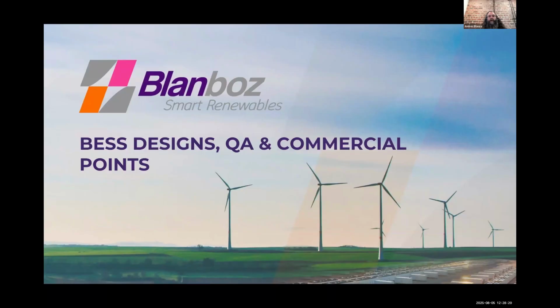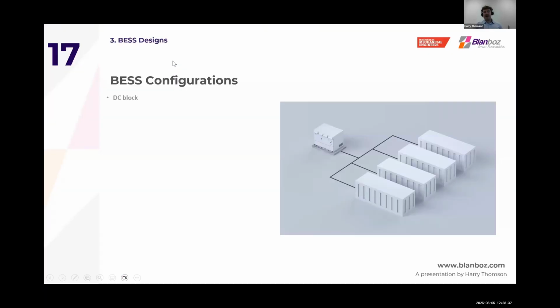So now let's move to Harry, who is going to delve deeper into the BESS design, quality assurance, and commercial points. Thanks, Andres. Yeah, I'm going to get straight into the design and talk about the products that are available at the moment. To begin with, typically we're seeing that batteries are being shipped in transportable containers, which house the cells, modules, and racks, as well as the ancillary systems, such as the cooling systems, power electronics, and the battery monitoring systems. At the moment, we're seeing two solutions offered. This is a DC block partnered with a central PCS, and an AC block partnered with string inverters. As you can see here with the DC block, depending on the project configuration, 1 to 4 containers are connected to that central PCS.